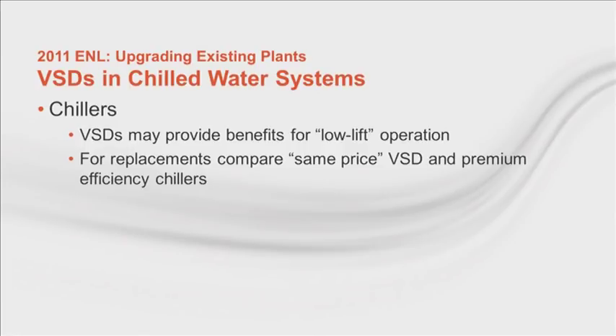It benefits operation when there are enough operating hours at low lift conditions, for example, when the tower water temperature can be reduced. If the chiller is to be replaced, compare 2 chillers with the same price, one with a variable speed drive and the other with more heat exchange surface and therefore premium efficiency. Perform an analysis with both demand and consumption costs. You can use the new MyPLV tool to calculate and compare annualized performance with your building type and climate with different chillers from any manufacturer.